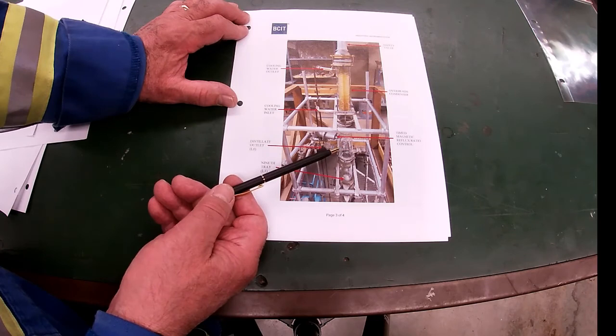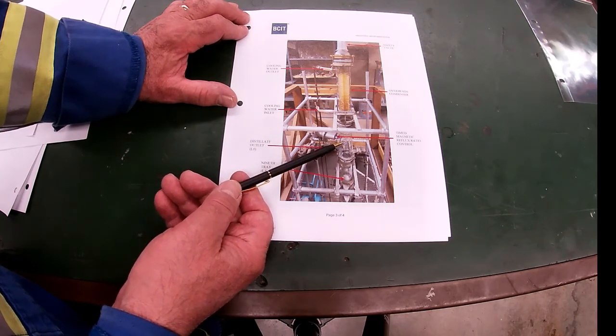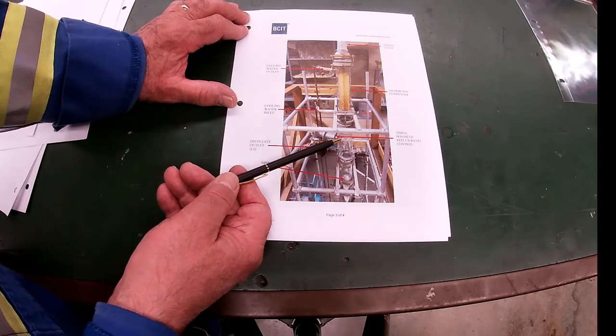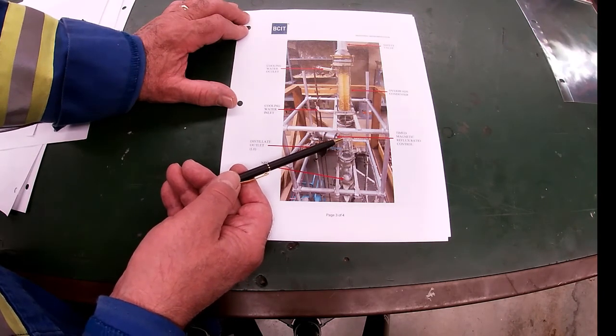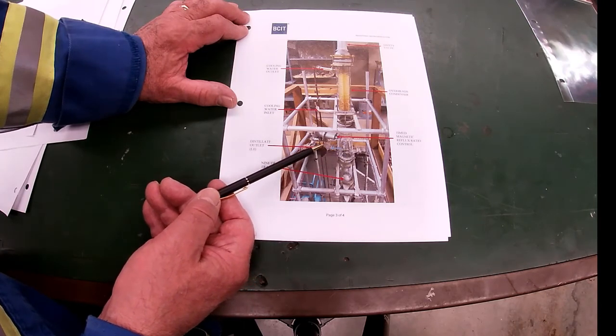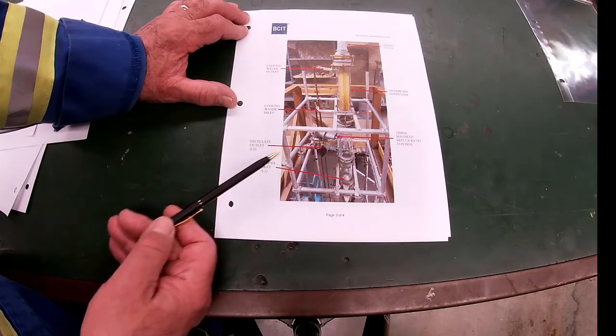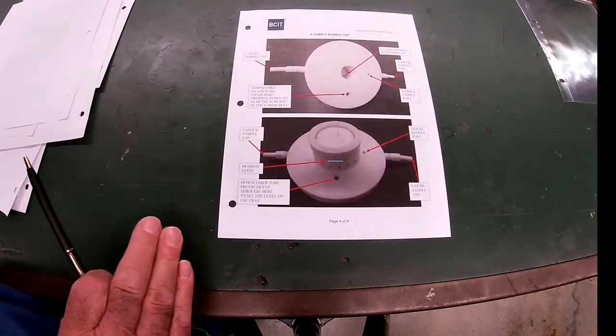The fact of the matter is that we run this column at total reflux, so we actually leave this valve closed so that this little magnetic control will switch back and forth, putting some reflux down here. Then when it flips over to put it in as a product out, it just overflows and goes down, and we end up, as I say, at 100% reflux.